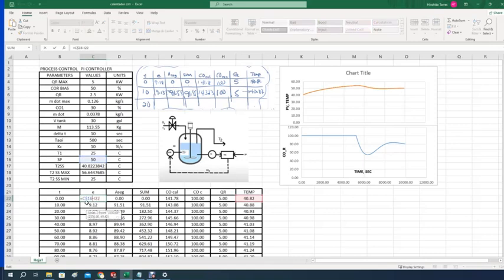The error is basically the set point 50 minus I22, which is this one here. Enter. What is the area of the segment? Remember, we are using a PI. The area of the segment, or the integral of that particular segment, since there the delta t is 0, you have an advance in time, that will be 0. The sum obviously is 0. So these 2 terms are used for the I part of the PI.